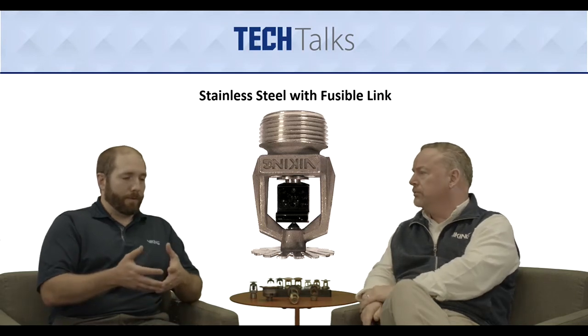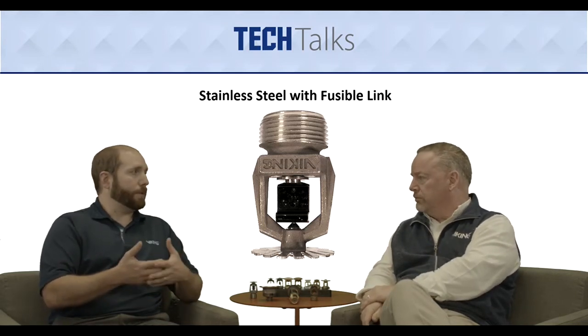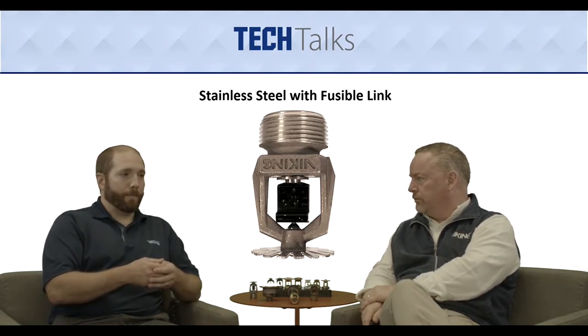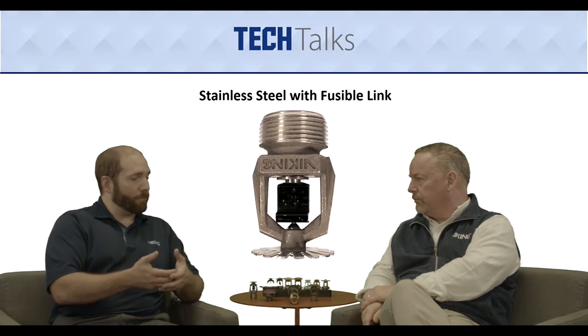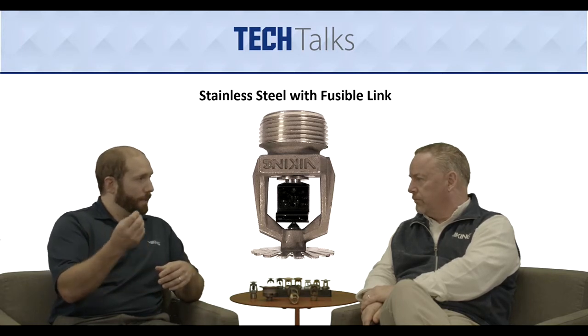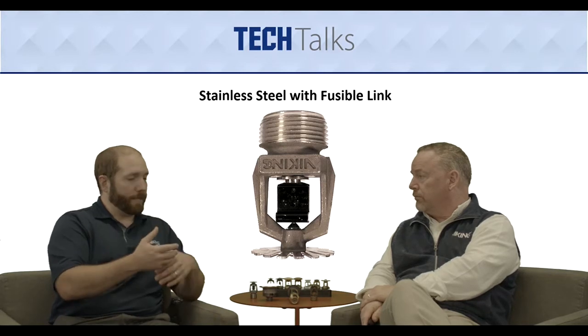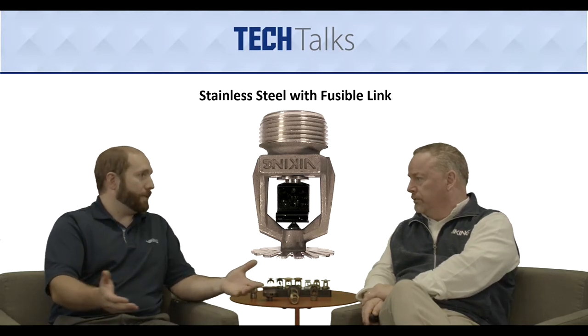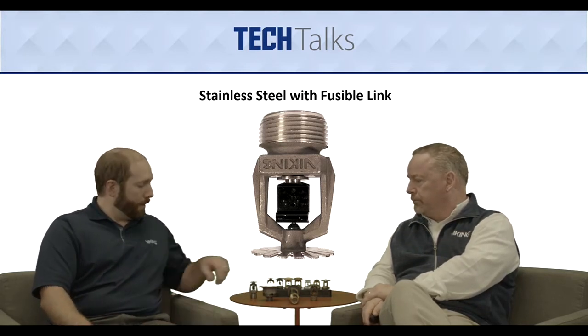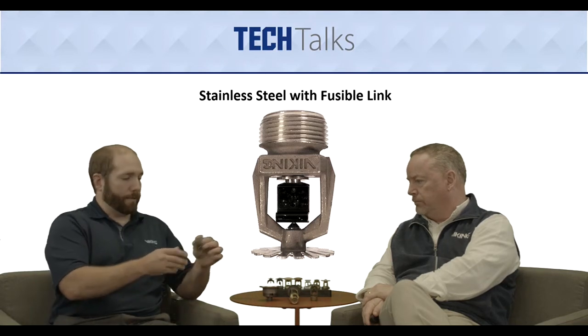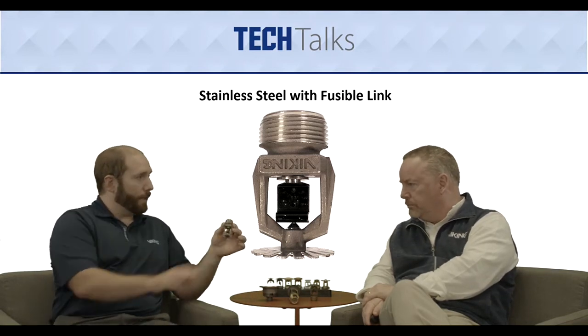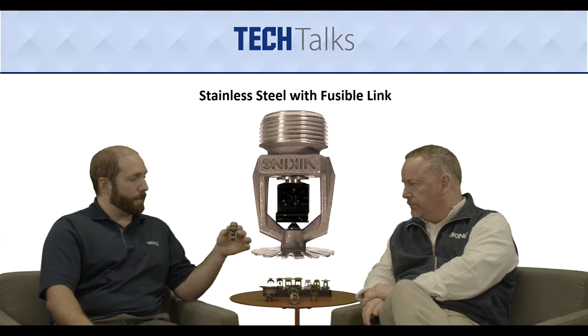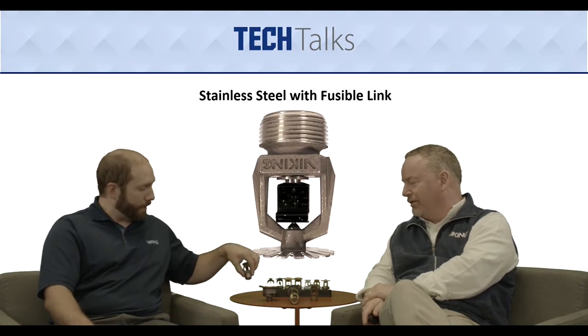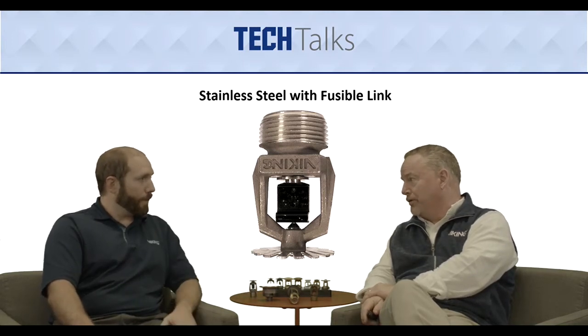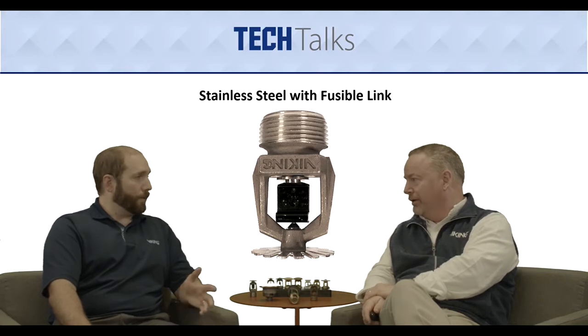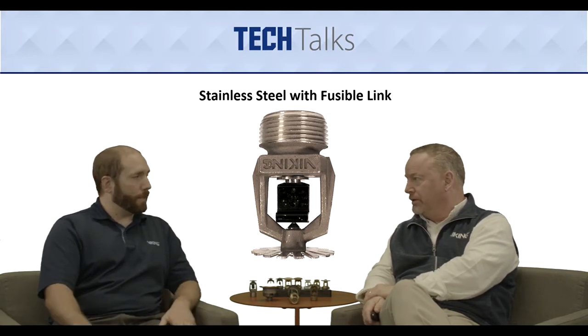So when we come across food facilities or storage, we want to use a metal link instead of a glass bulb, because if that glass bulb shatters from activation, now we've got glass within that space. Here, with the fusible link, we've got a metal link, so we can just go find it. Go find the parts. There's probably two parts to it and the pip cap, and you're pretty much done. A lot better than a lot of little glass pieces.